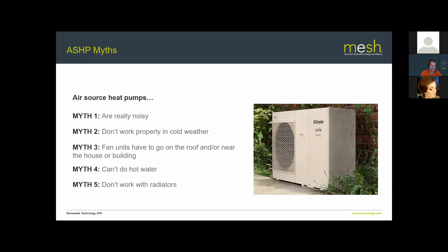Myth five: heat pumps don't work with radiators. Also not true — heat pumps work perfectly well with radiators as long as sizing is correct. You want to reduce the flow temperature from the heat pump as far as possible to maximise the COP, which might mean upsizing some radiators or using large double or triple-finned radiators rather than conventional single-finned ones. As long as the system is correctly sized, radiators work fine.